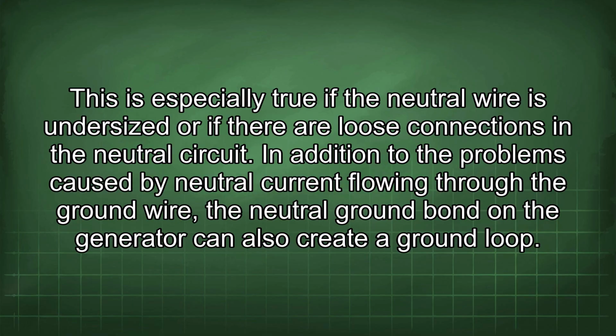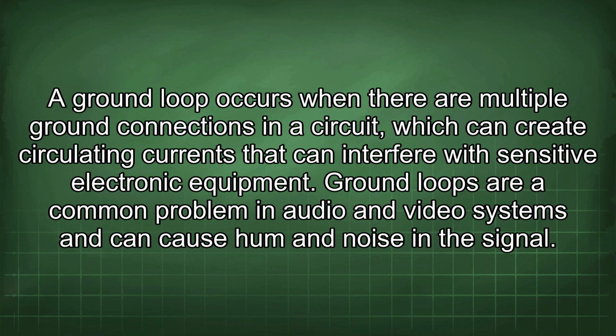In addition to the problems caused by neutral current flowing through the ground wire, the neutral ground bond on the generator can also create a ground loop. A ground loop occurs when there are multiple ground connections in a circuit, which can create circulating currents that can interfere with sensitive electronic equipment. Ground loops are a common problem in audio and video systems and can cause hum and noise in the signal.